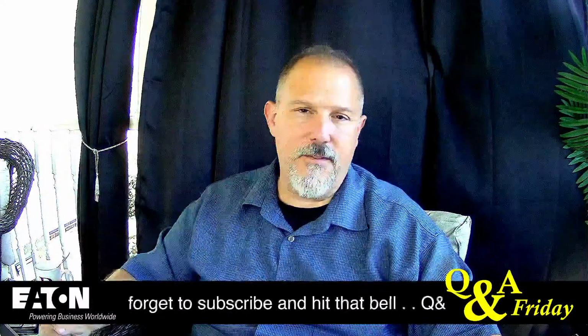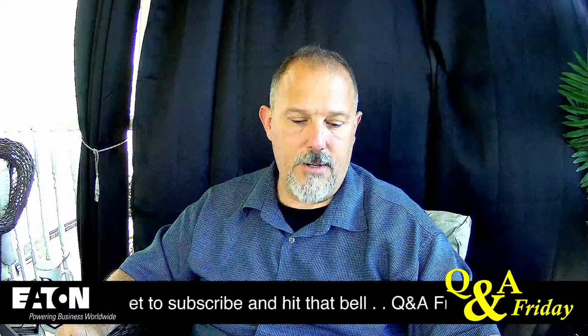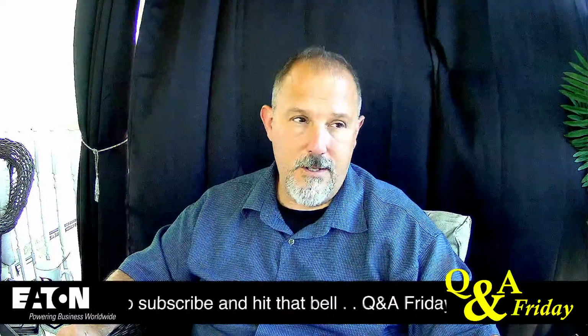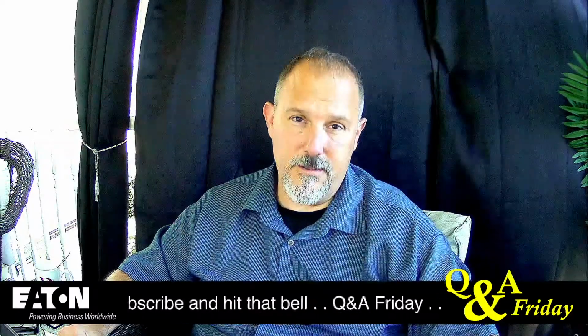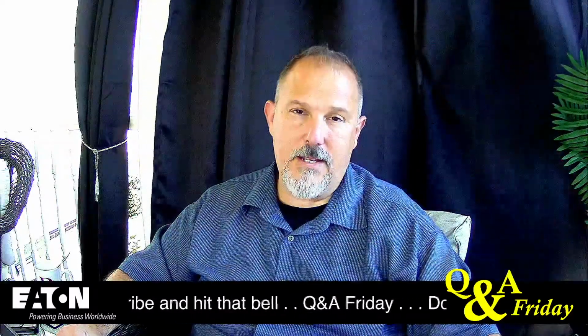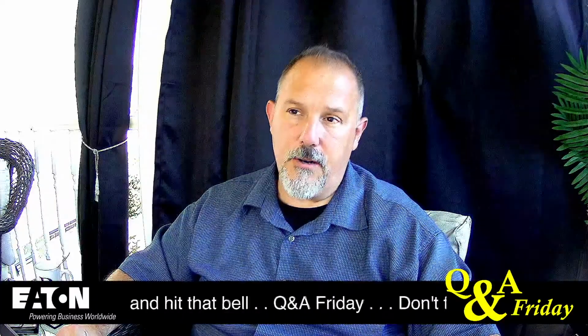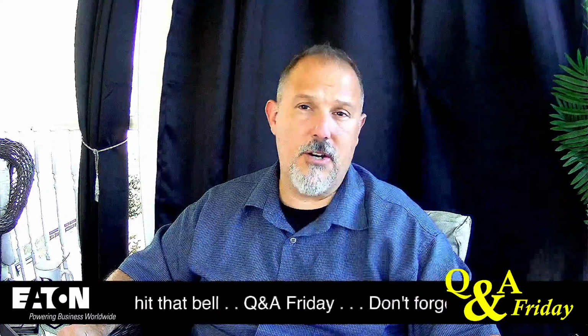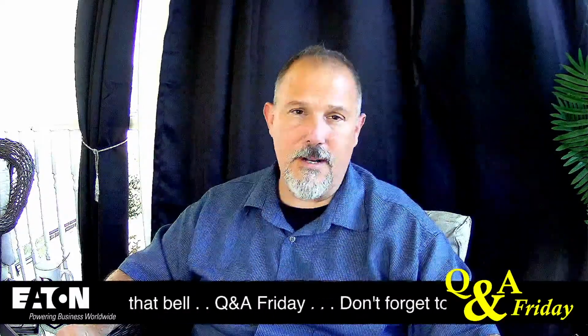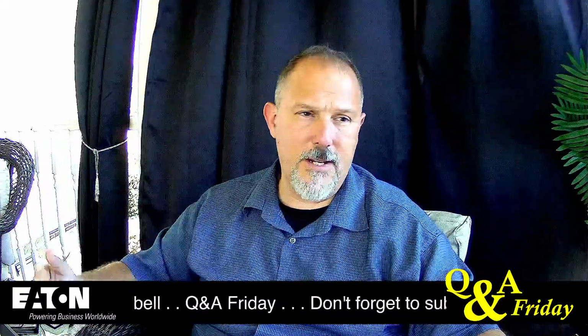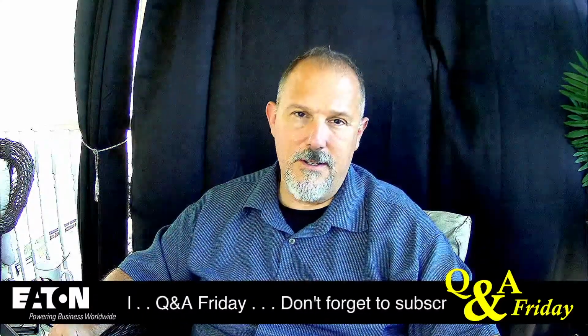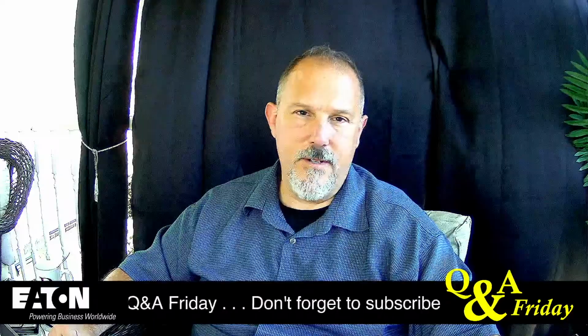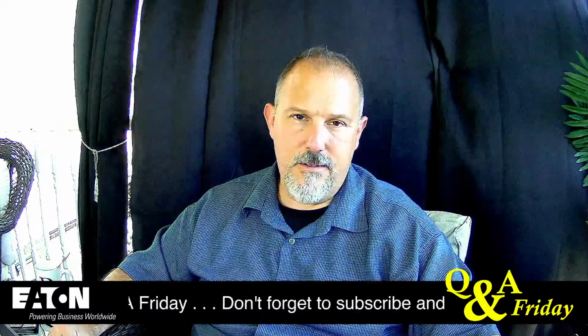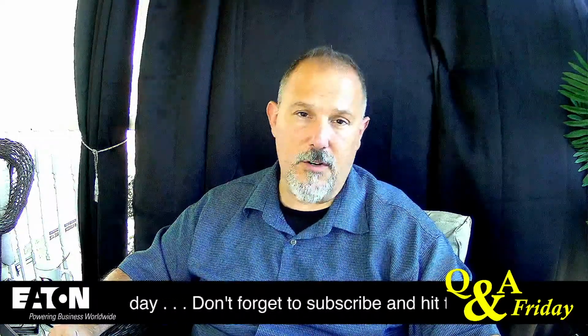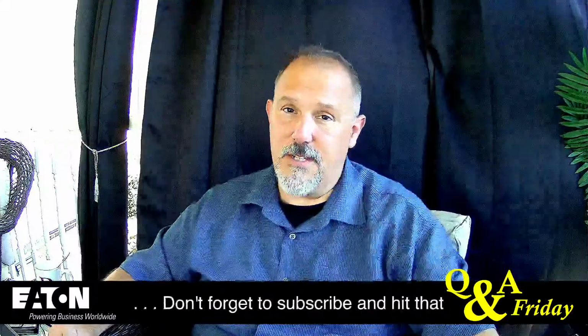And I would love to do that test. I probably will this year, maybe next year. Run that test and show that a current limiting device, or a circuit breaker in its instantaneous region, clearing in less than 2 cycles, you're not going to have enough energy in the air to go to the line side of that main overcurrent protective device, especially if it's in a barrier.